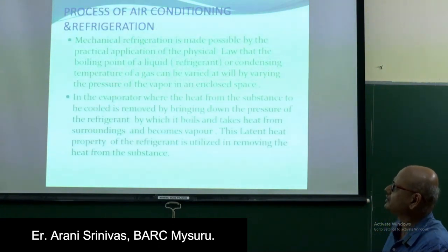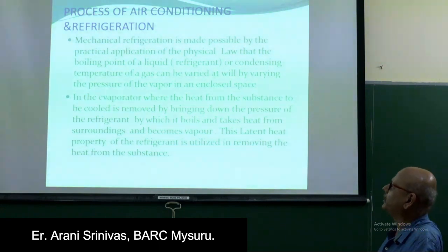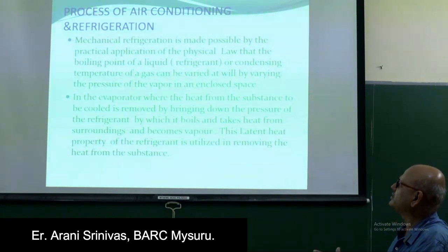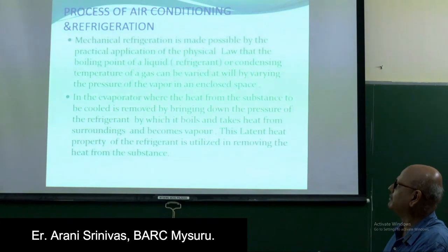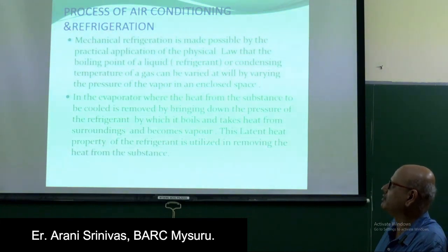Now, mechanical refrigeration is made possible by the practical application of a physical law: the boiling point of a liquid, that is the refrigerant, or the condensing temperature of a gas, can be varied at will by varying the pressure of the vapor in an enclosed space.